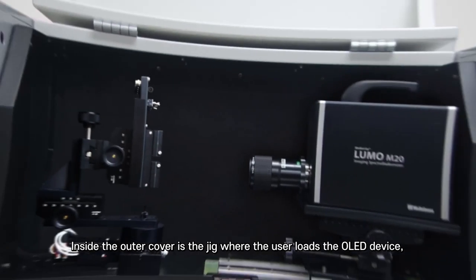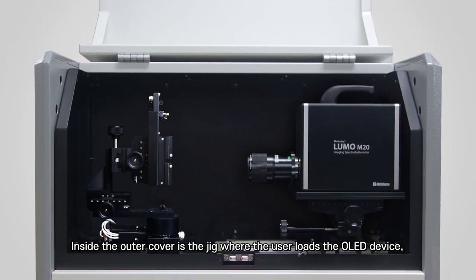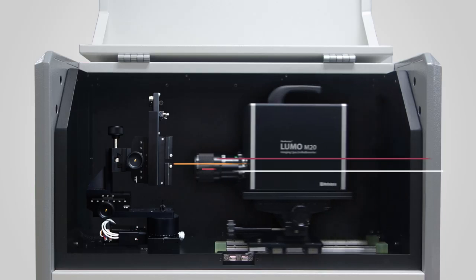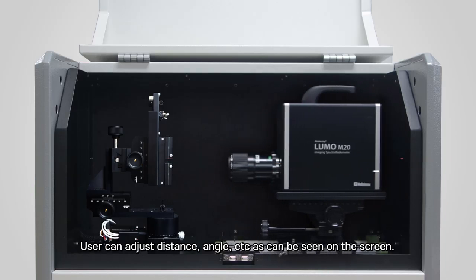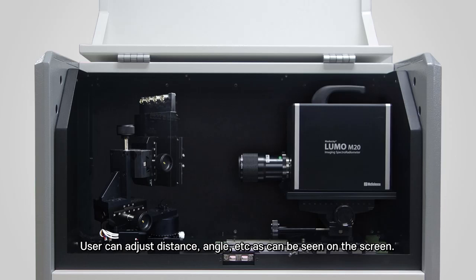Inside the outer cover is the jig where the user loads the OLED device, the motion stage, and the spectrometer. The user can adjust distance, angle, etc., which can be seen on the screen.